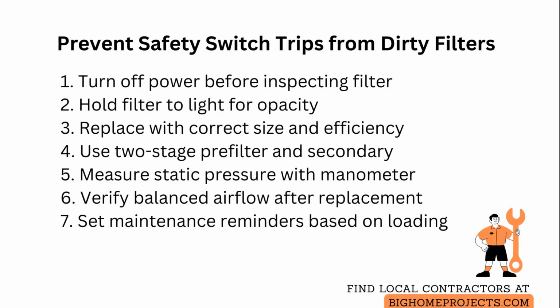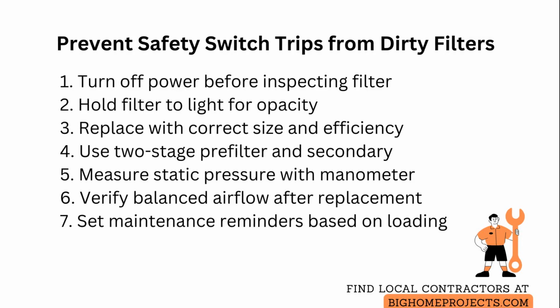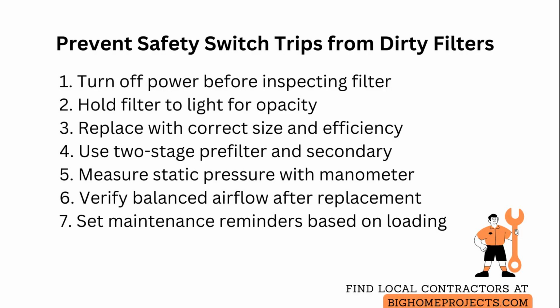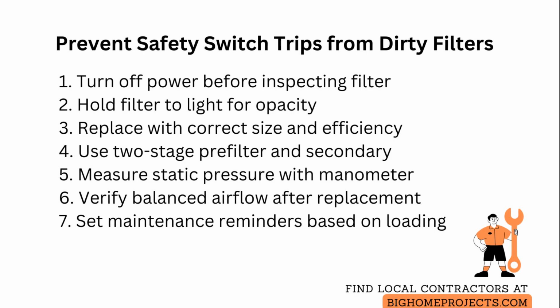Finally, if safety switches continue to trip after filter and airflow checks, inspect motors and bearings for excessive current draw and verify ductwork is not collapsed or blocked. Then consult a trained technician for electrical diagnosis.